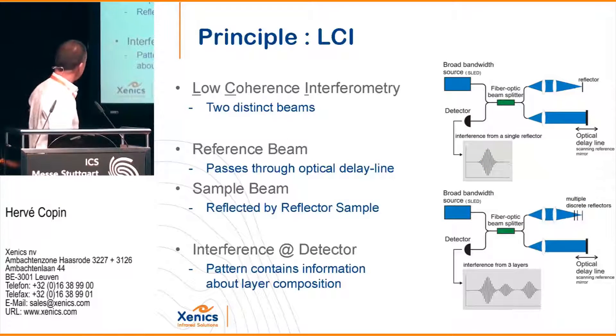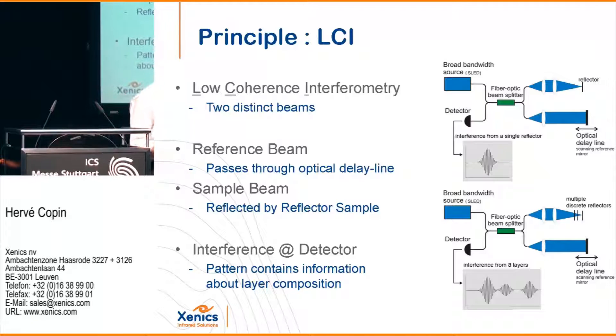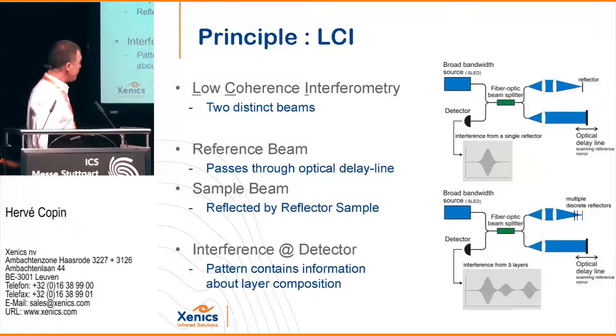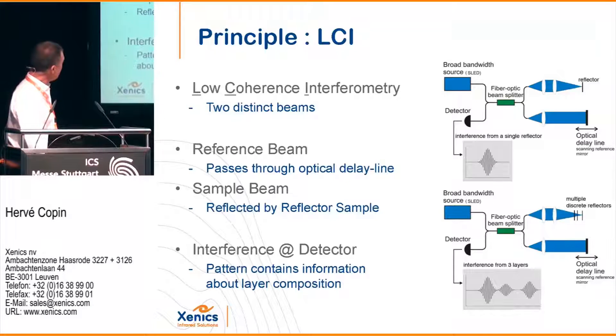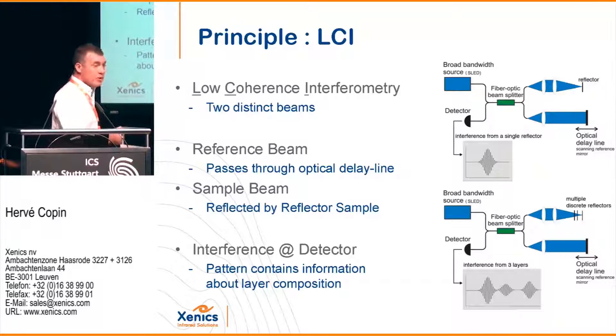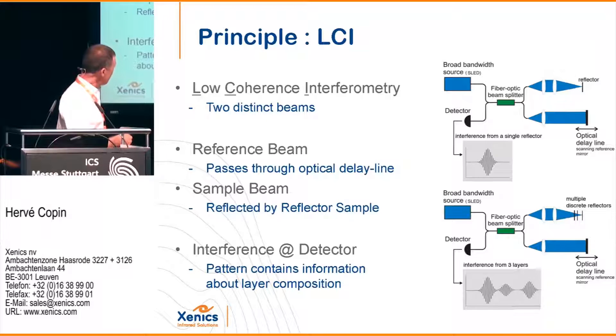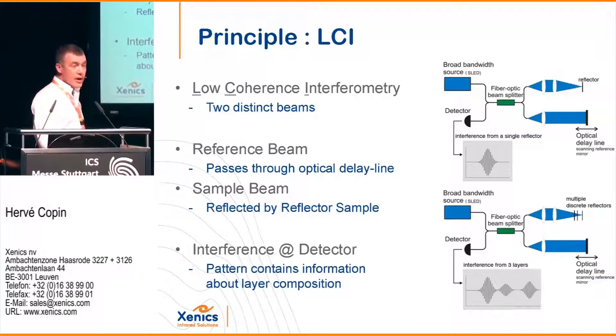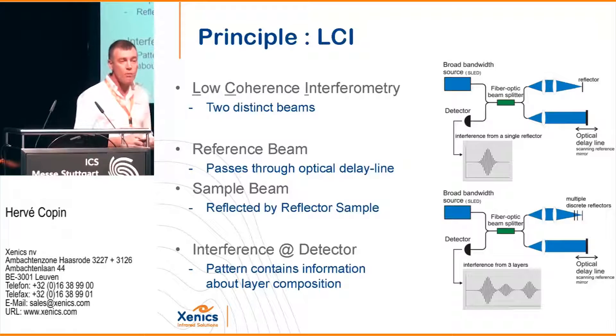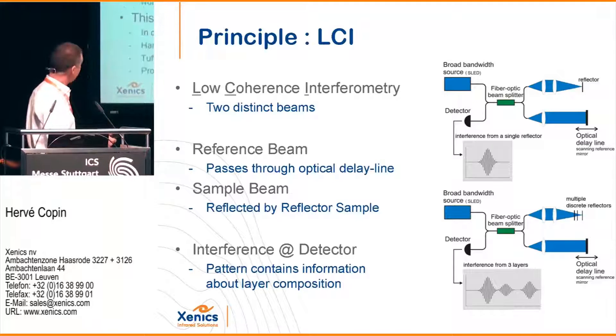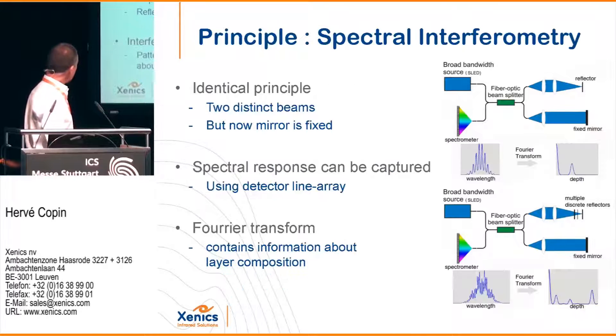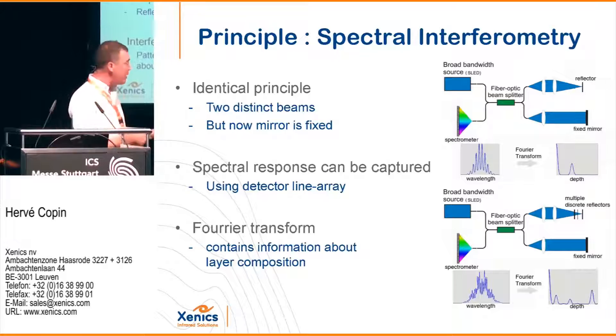What is low-coherence interferometry? There are two techniques: one based on time domain and another based on spectral measurements. The idea is simple — it is an interferometer with a broadband source such as a super-bright LED. You go through a beam splitter and the beam is split in two: one path to a reference reflector and the other to the sample. Recombining the signal creates an interference image that gives information about the surface of the object. If the sample has multiple layers, you get an image of all those layers.